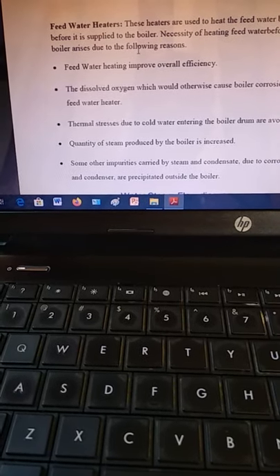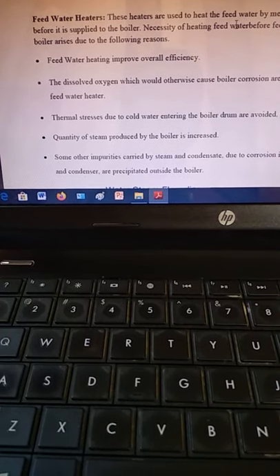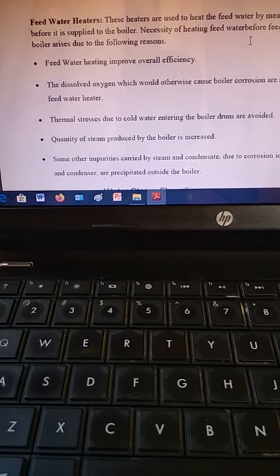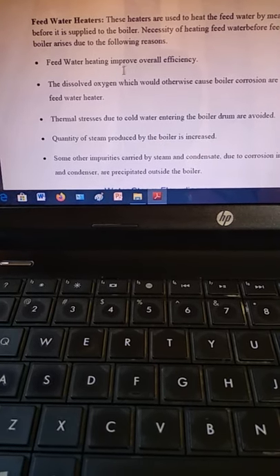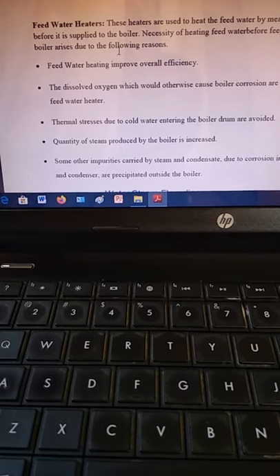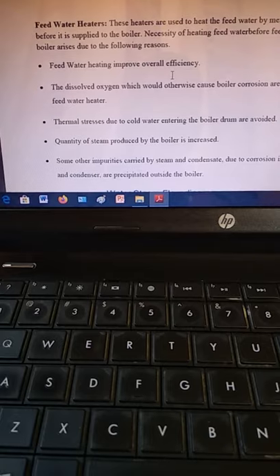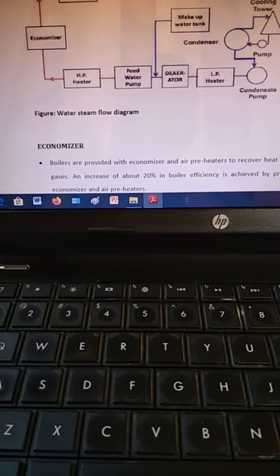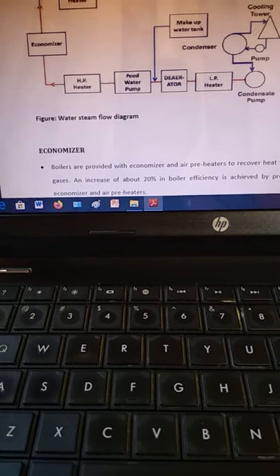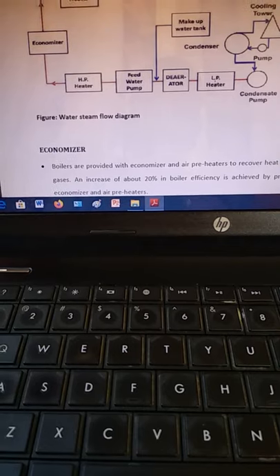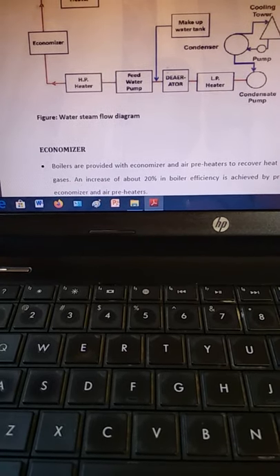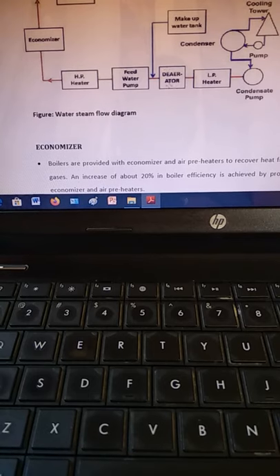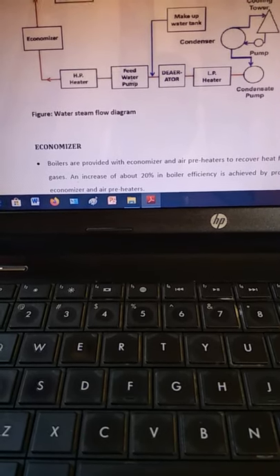Feed water heaters are used to heat the feed water by means of bled steam before it is supplied to the boiler. The necessity of heating feed water before feeding it back to the boiler arises due to specific reasons. Feed water heating improves overall efficiency. In the systematic diagram of the water-steam flow, you can see the cooling tower, pump, condensate pump, low-pressure heater, and deaerator. The deaerator removes oxygen and other dissolved gases from the feed water.